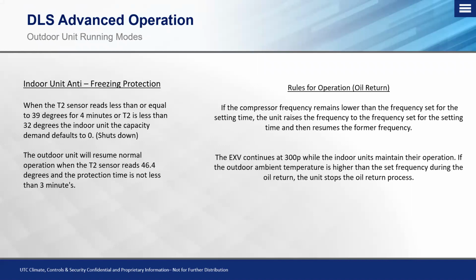Okay, so we look at the rules for operation for oil return. This is usually another common question that comes up whether I'm on site or during classes. So we look at oil return being a fixed period of time where the compressor has been running at a part load scenario or that target frequency.